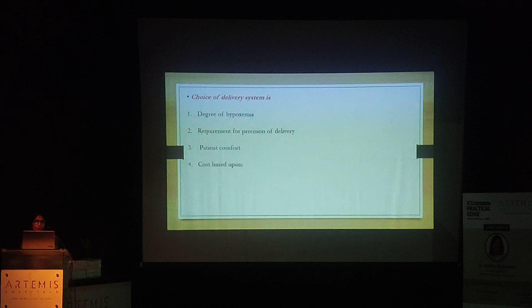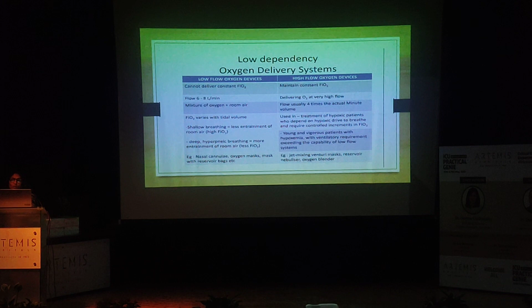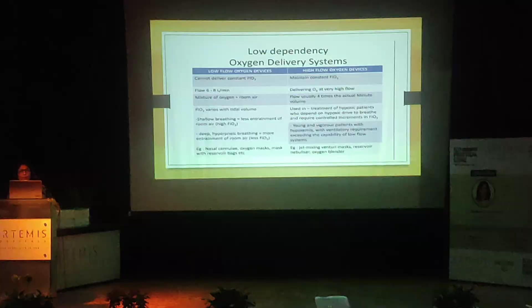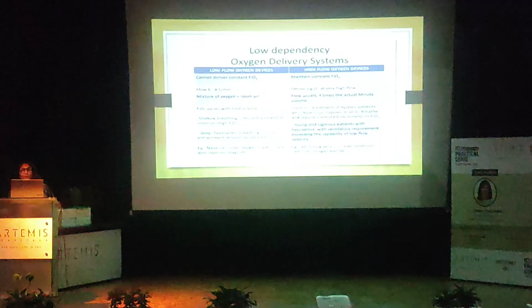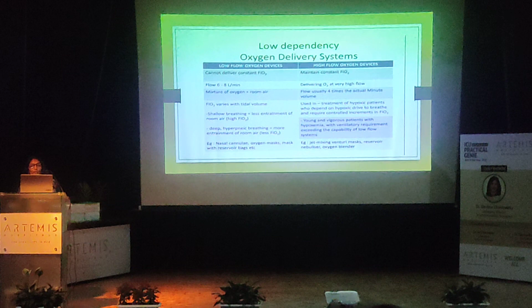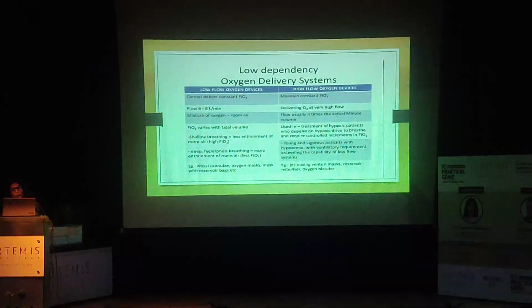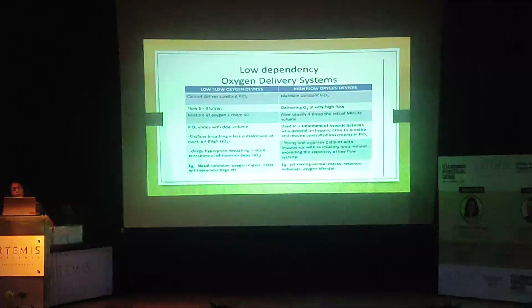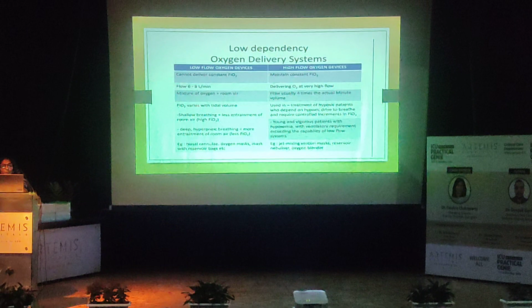Now the low dependency systems, we'll start with that. The low flow systems can be classified again into nasal cannula, simple mask, reservoir mask. The low flow oxygen delivery systems cannot deliver a stable FiO2. There is always a variation in the oxygen that reaches the patient. Whereas the high flow devices usually maintain a constant FiO2. The flows are usually between 6 to 8 liters in a low flow system, whereas the fixed flow systems have a very high oxygen flow rate ranging from 20 to 40 up to 50.